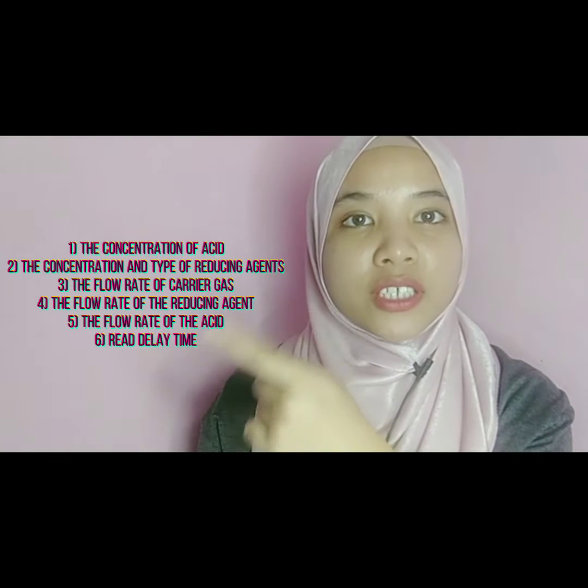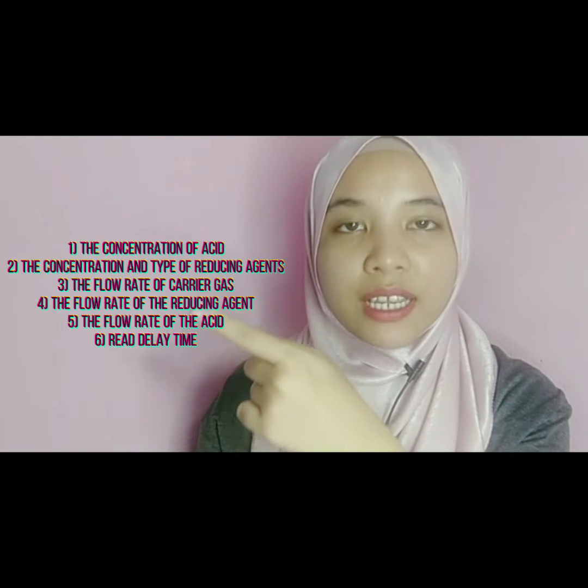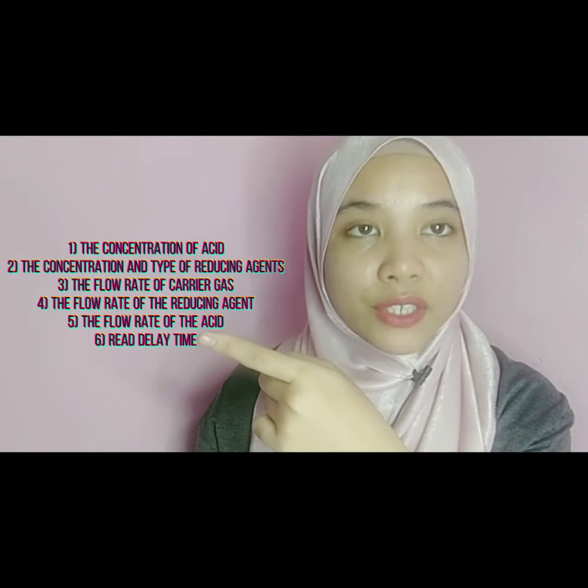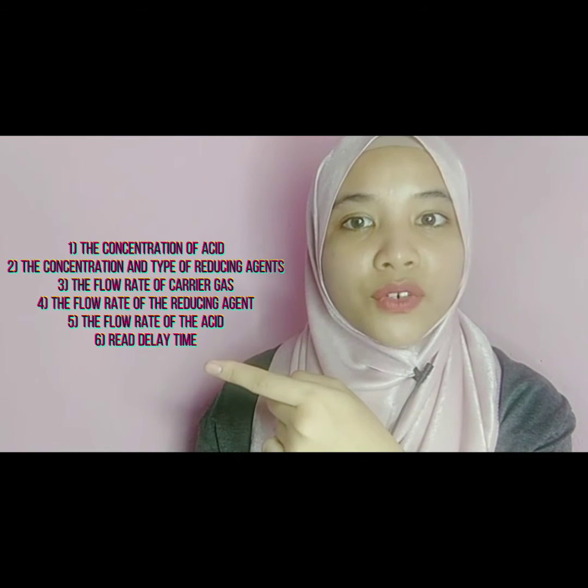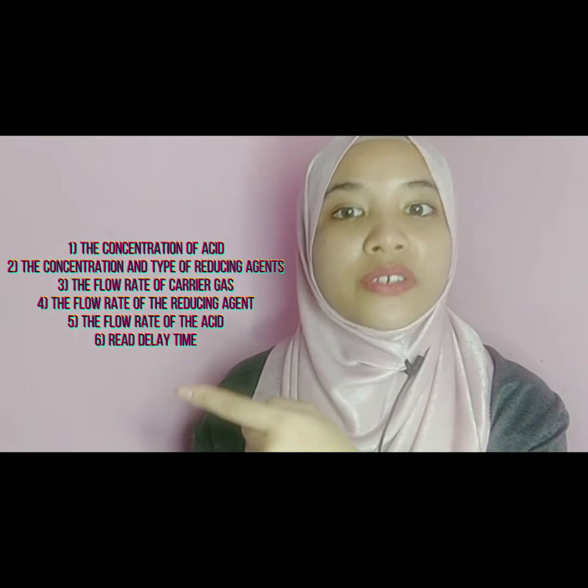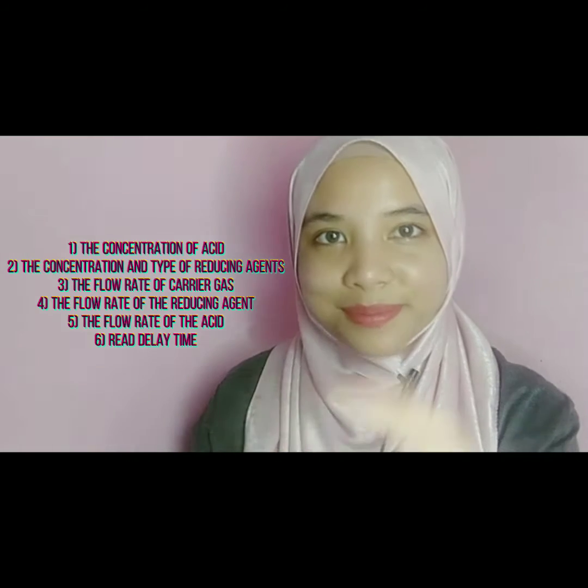The factors that will influence the optimization of the hydride generation AAS are the concentration of the acid, the concentration and the type of reducing agent, the flow rate of the carrier gas, the flow rate of the reducing agent, the flow rate of the acid, and also the read delay time of the sample. On the other hand, the cold vapor AAS is the most sensitive method for mercury determination compared to flame AAS since it gives more sensitivity.